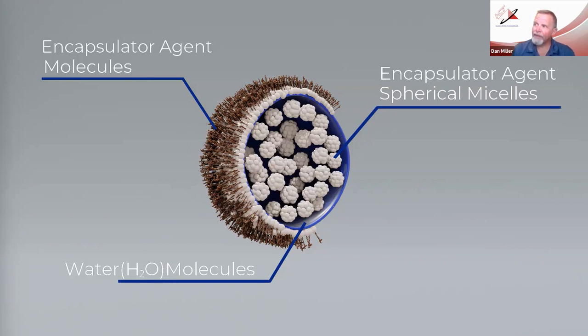Inside each of those spherical micelles are the trapped carbons and hydrocarbons that would otherwise be the fuel for combustion. It traps those as it's flying through the air towards the object on fire or the liquid fuel on fire, pulling them out of the vapor space above the fire. It also traps them when it strikes the fuel surface, agitating a liquid fuel, for example, and encapsulating the carbons and hydrocarbons out of the liquid fuel as well.